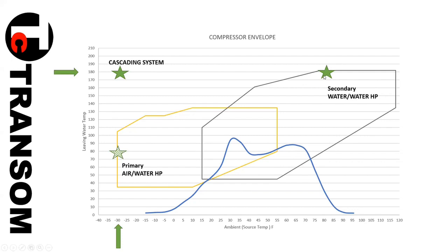If you were doing this exact job in a crazy polar vortex, which might really only be a day or just an evening, where you got to negative 30, but just in that most extreme circumstance, which is less than 1% of 1% of a year, when that happened, what would be its COP going from negative 30 up to 180? What's the low COP? Yeah, in round numbers, these two here with the fans, I didn't refine the fans, but it would be about 2.4, somewhere in there. Awesome. That's fantastic.